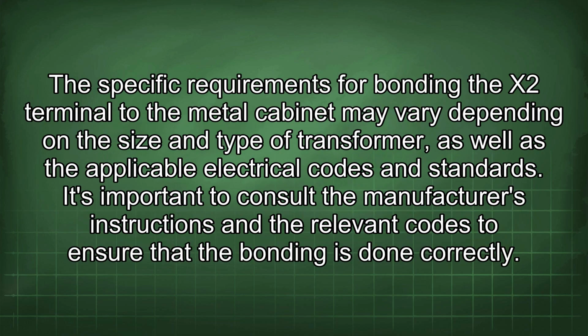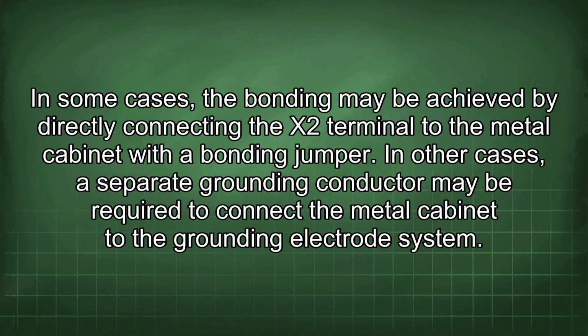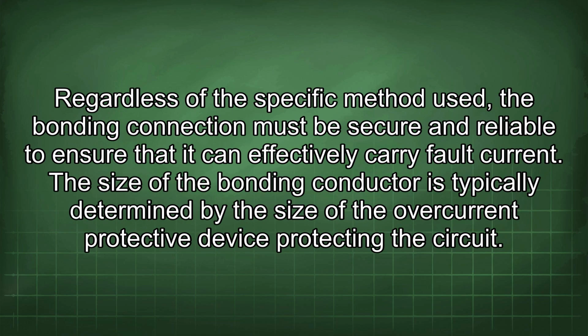The specific requirements for bonding the X2 terminal to the metal cabinet may vary depending on the size and type of transformer, as well as the applicable electrical codes and standards. It's important to consult the manufacturer's instructions and the relevant codes to ensure that the bonding is done correctly. In some cases, the bonding may be achieved by directly connecting the X2 terminal to the metal cabinet with a bonding jumper. In other cases, a separate grounding conductor may be required to connect the metal cabinet to the grounding electrode system. Regardless of the specific method used, the bonding connection must be secure and reliable to ensure that it can effectively carry fault current.